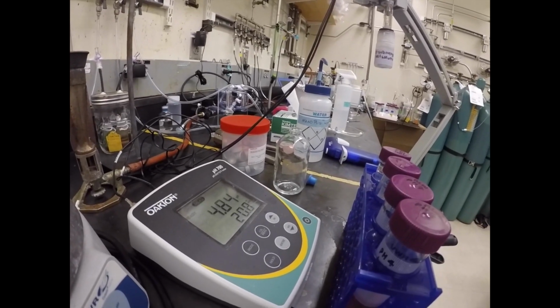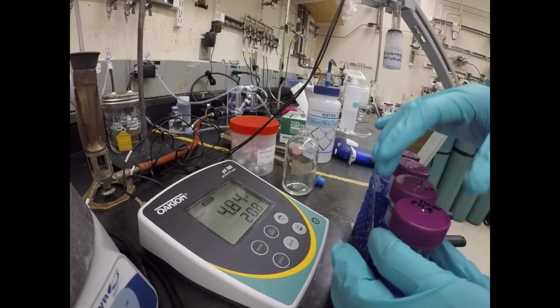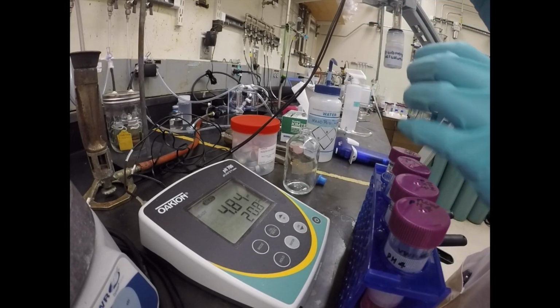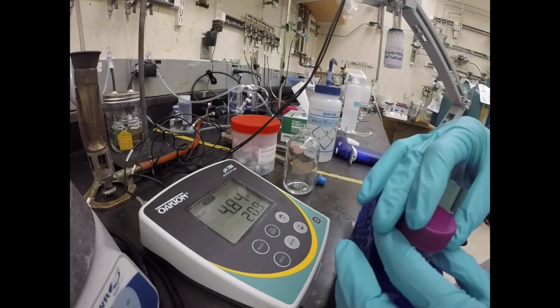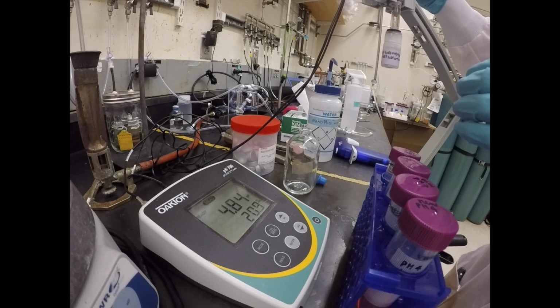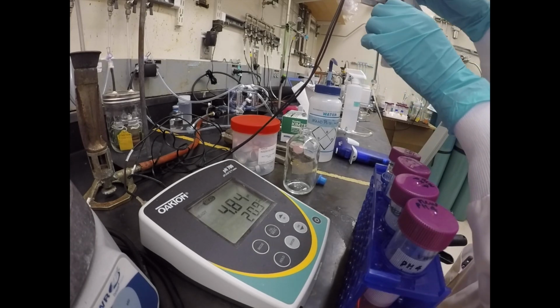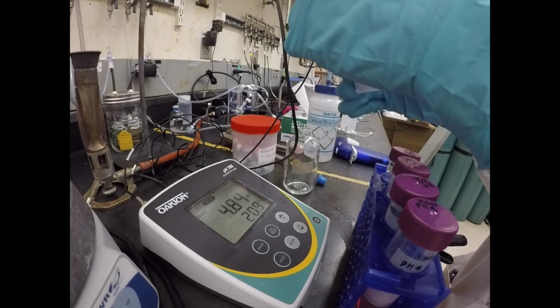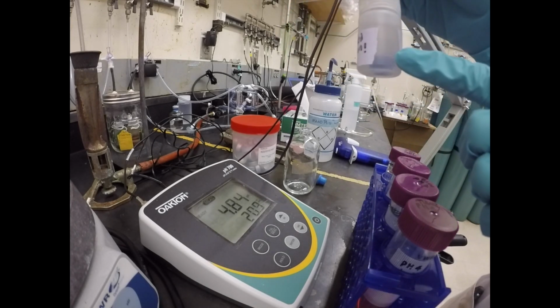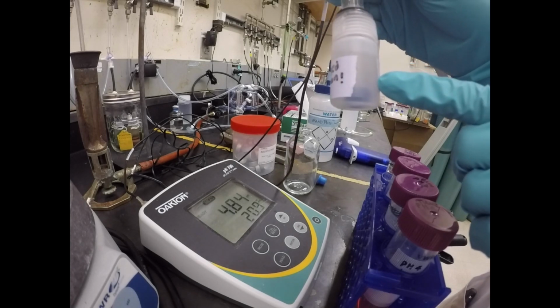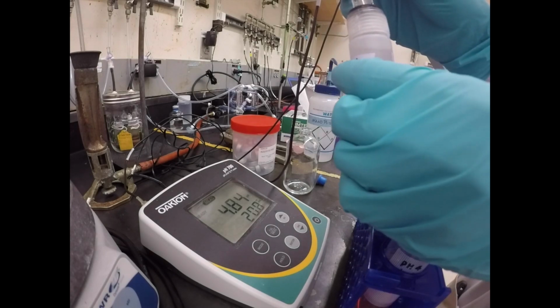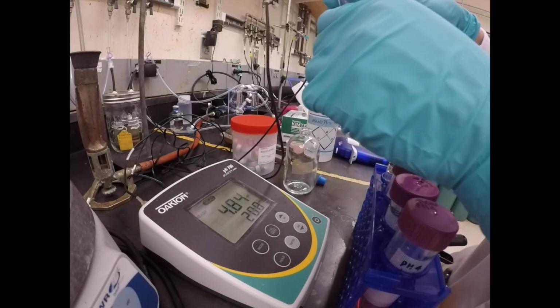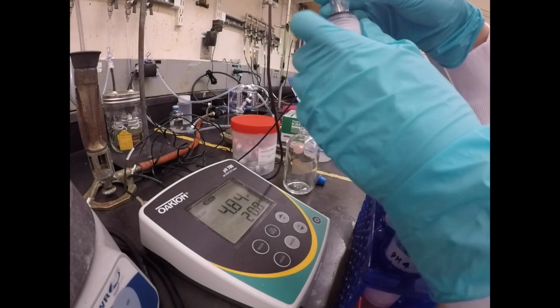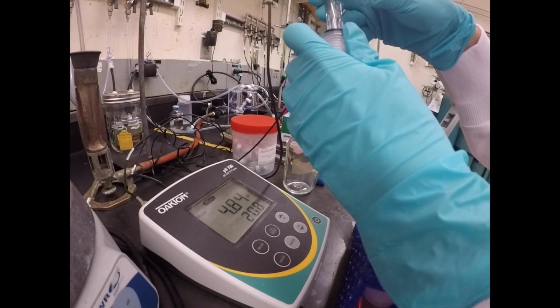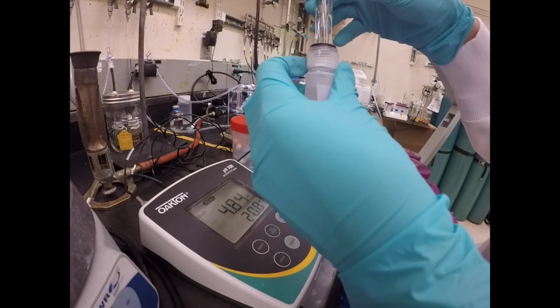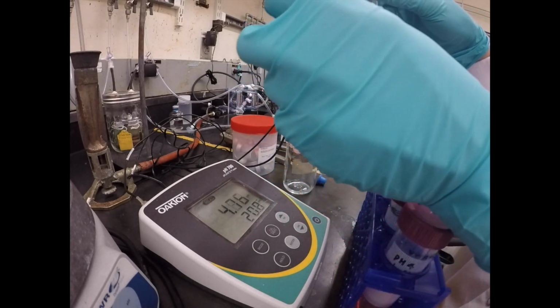So in order to calibrate your pH probe, you're going to submerge the tip of your pH probe inside a standard solution. And it's important to do that with a temperature probe. And I'm going to gently take this off. This is normally stored in this pH probe storage solution that is saturated with potassium chloride. And just be careful not to touch the tip of the pH probe, because that can be very sensitive. So just slide this off after you've opened the cap of this.